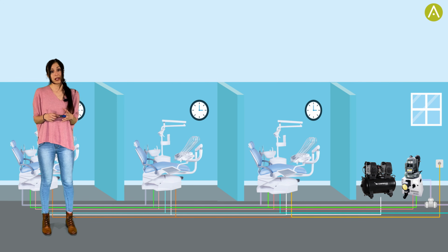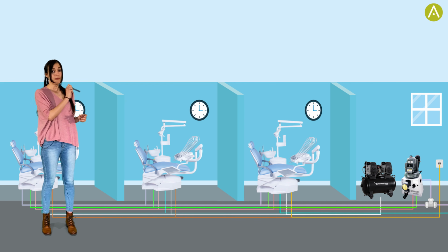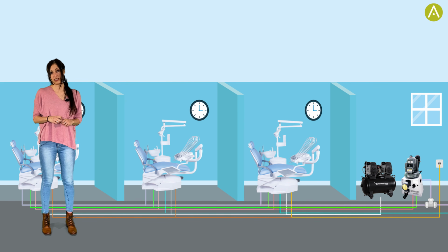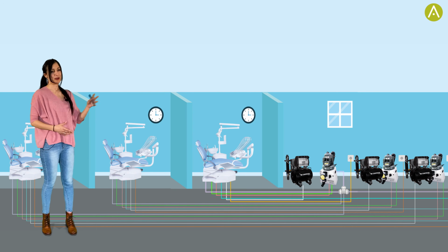This is not the most convenient solution, since with it you would not have the benefits of having one compressor and suction system per unit, avoiding loss of service if one stops working. On top of this, we would also need to install shut-off valves on each of the dental units. This is a very inefficient system, that's why we always recommend the first option, which you can see here again.